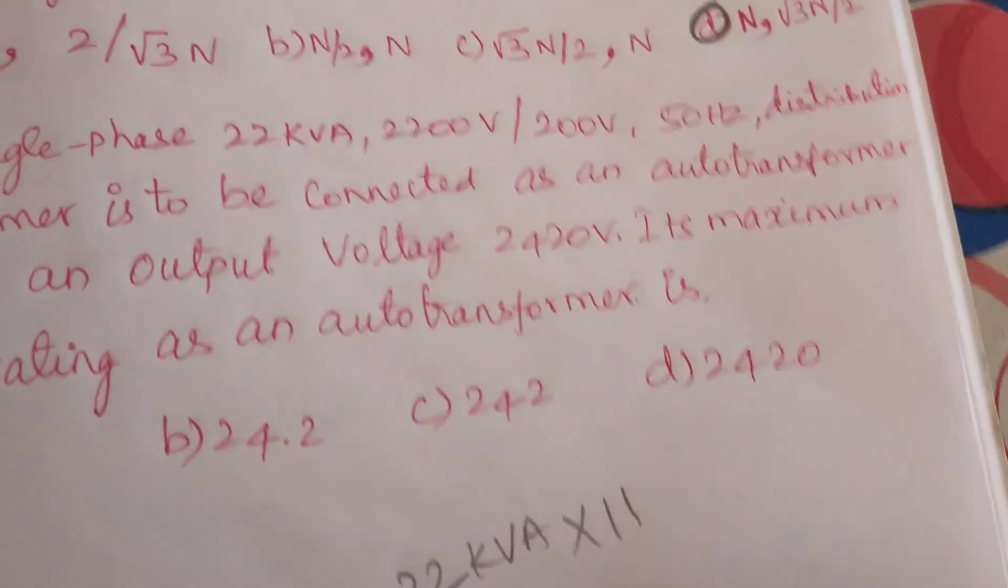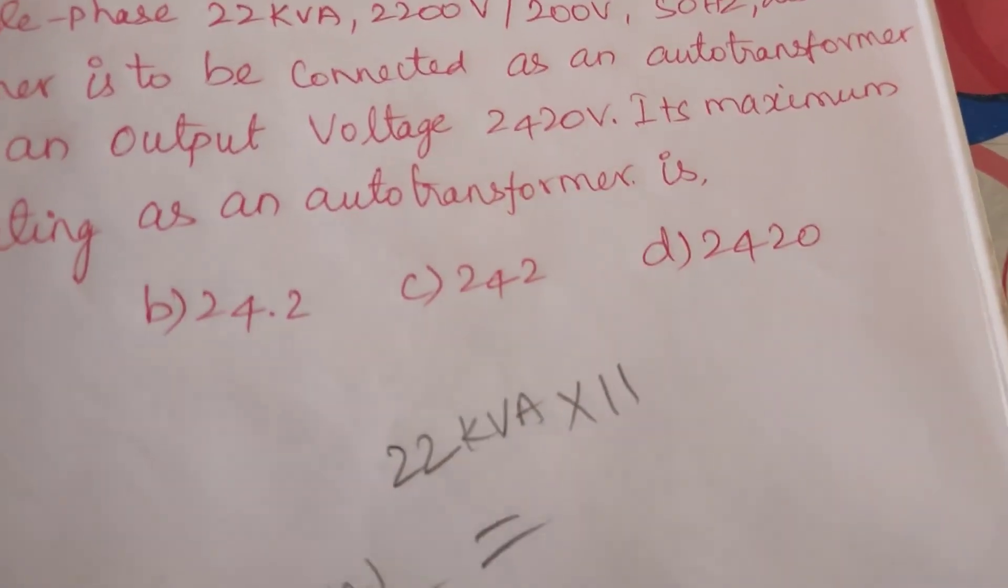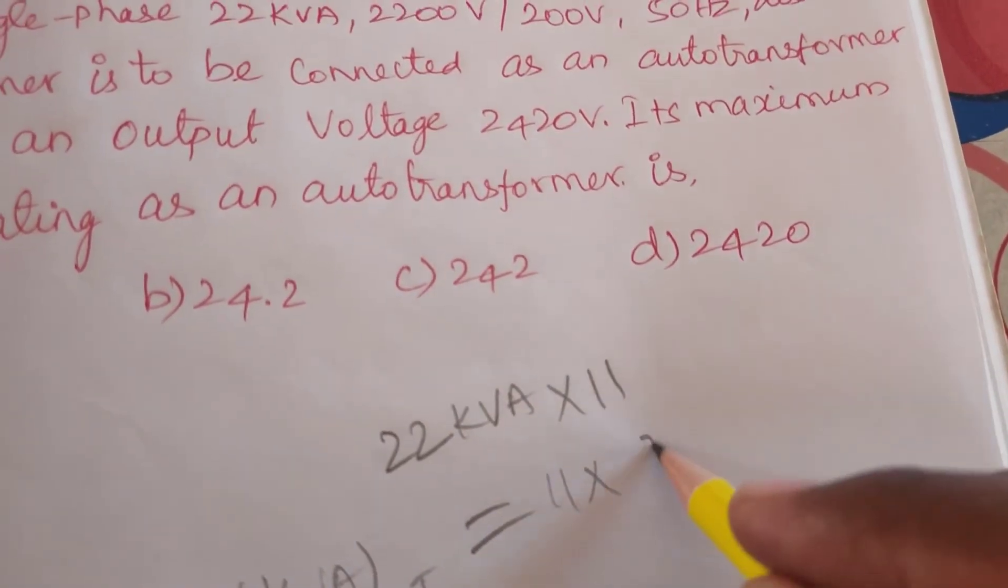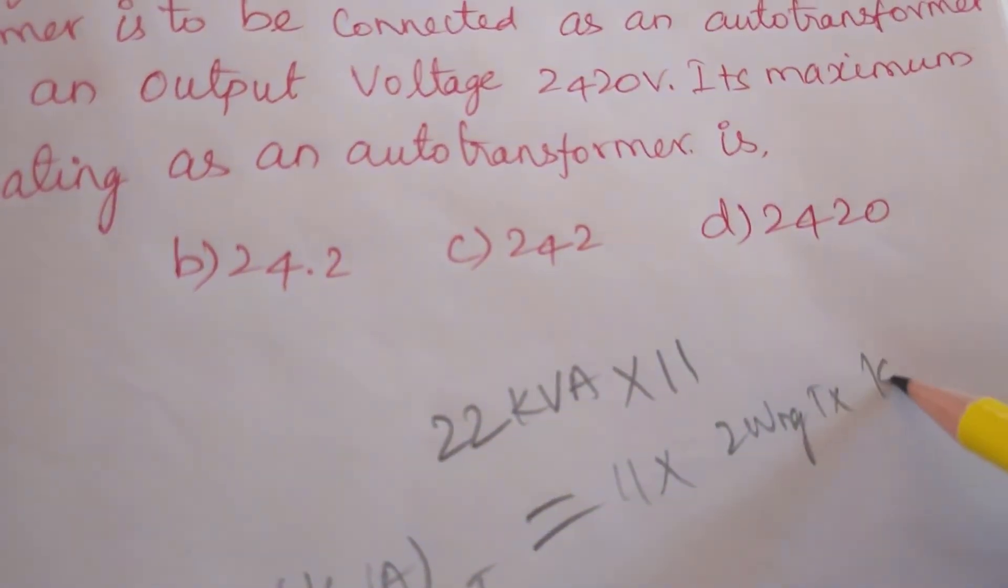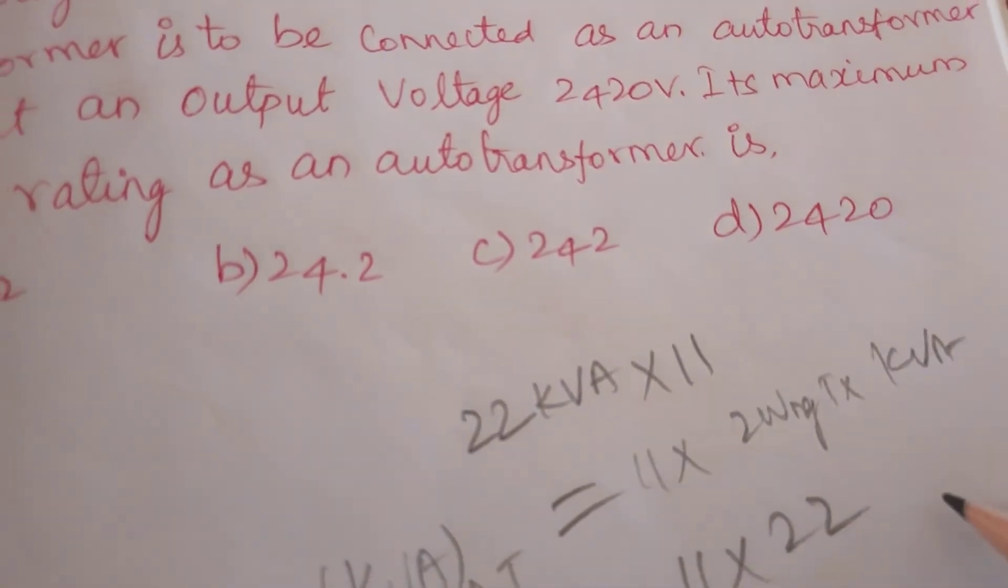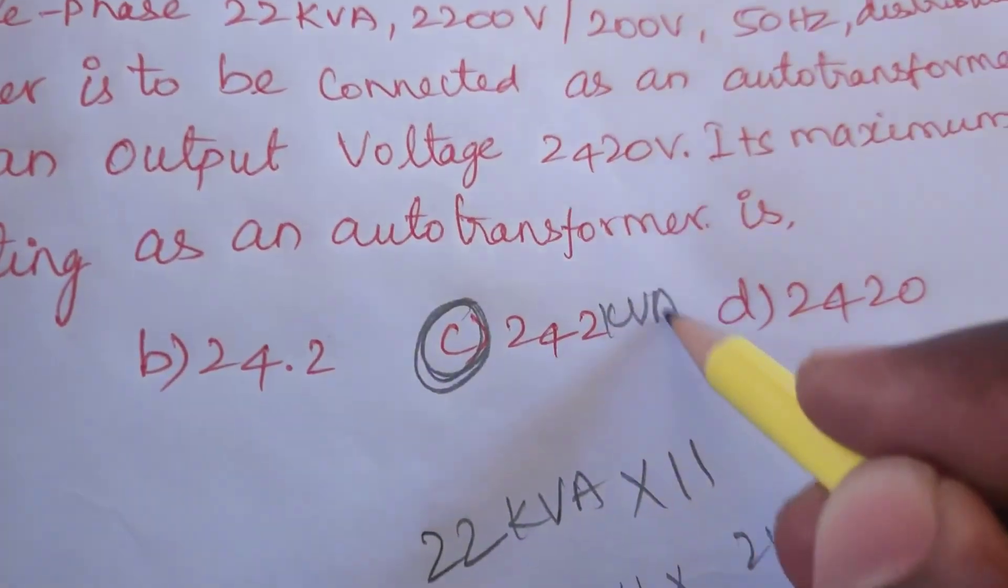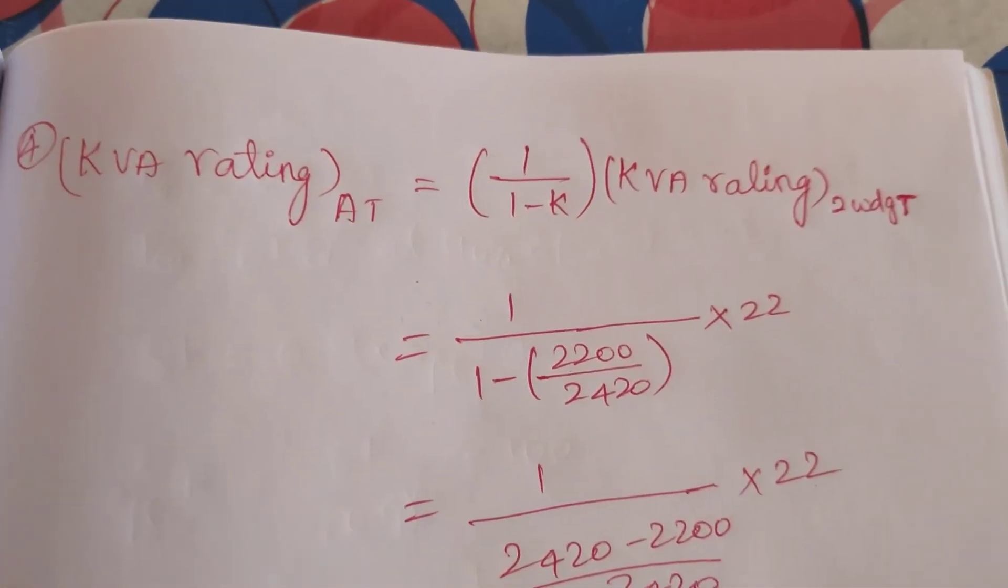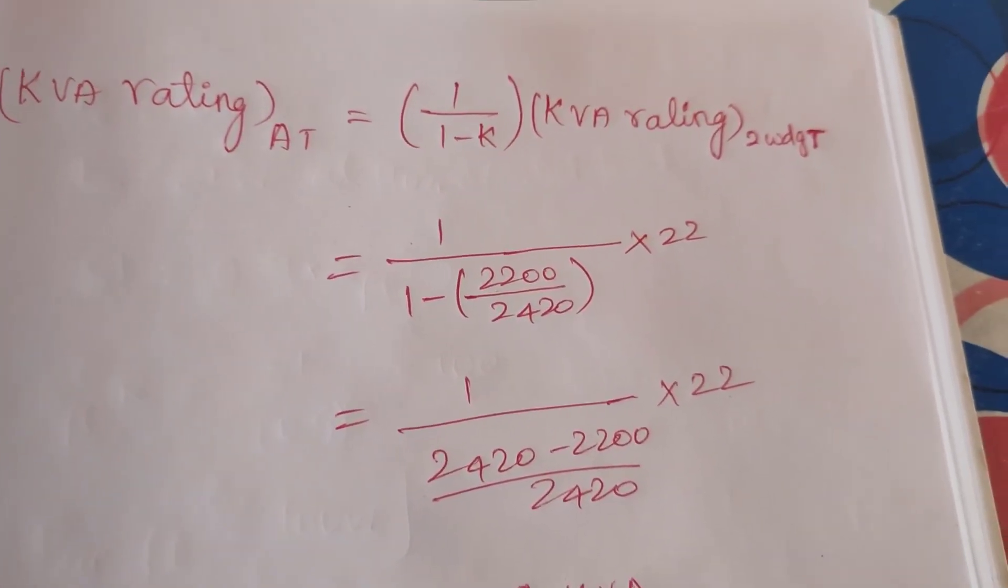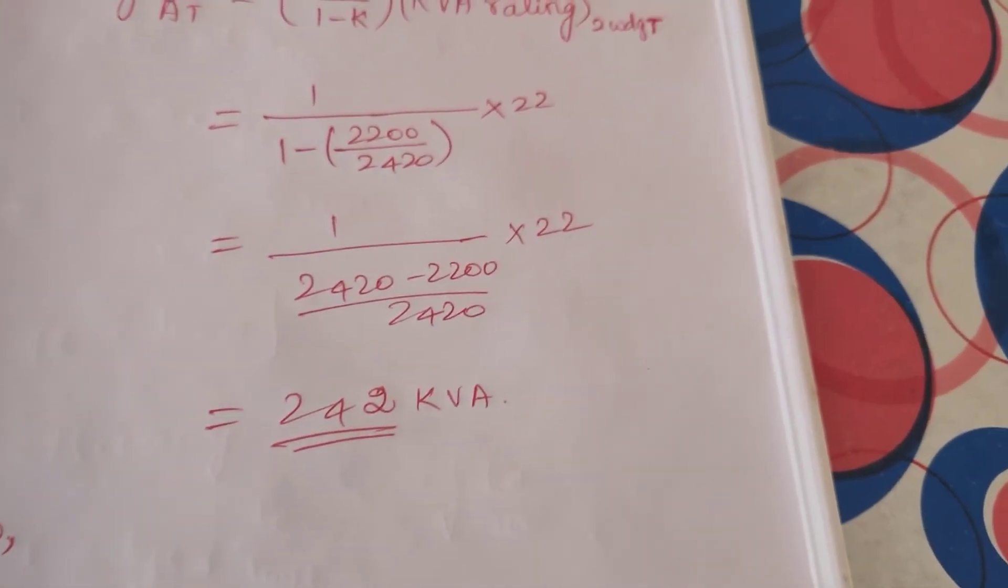Auto transformer kVA is equal to 11 into two winding transformer kVA. So 11 into 22 we will get 242 kVA. Or otherwise the formula: kVA rating auto transformer is equal to 1 by (1 minus k) into kVA rating of two winding transformer. So we will get 242 kVA.